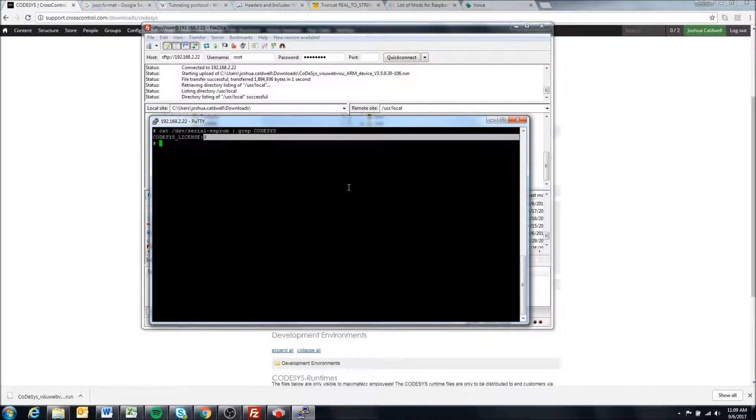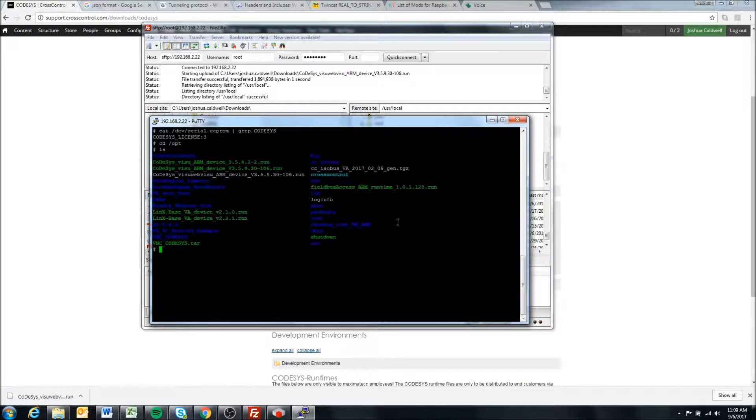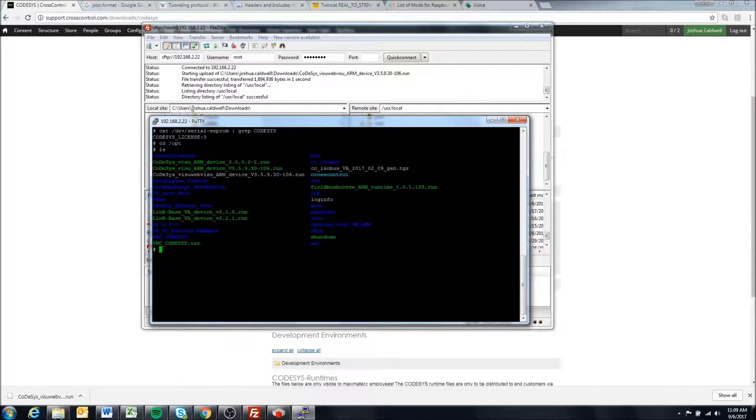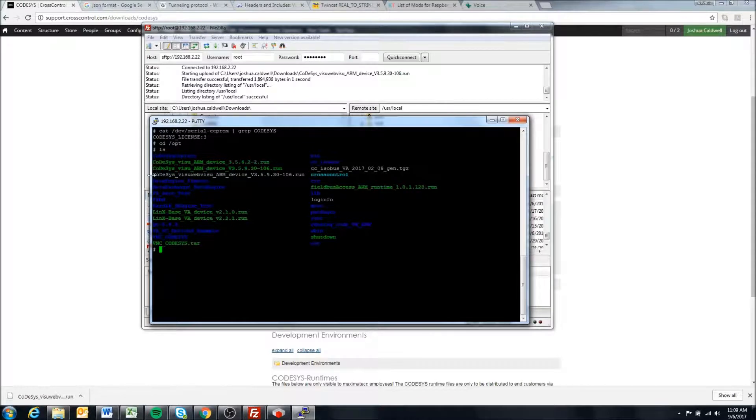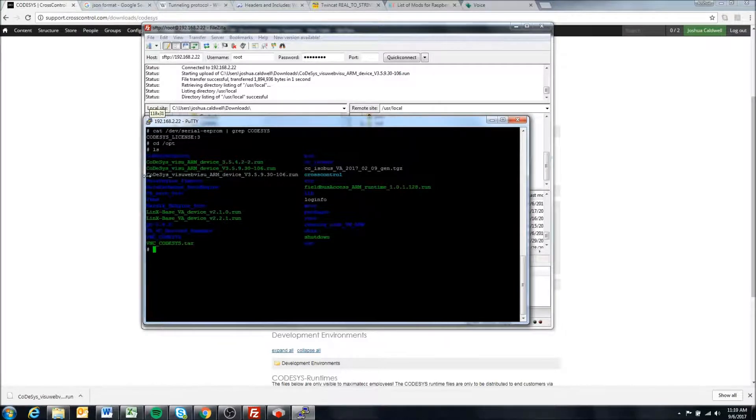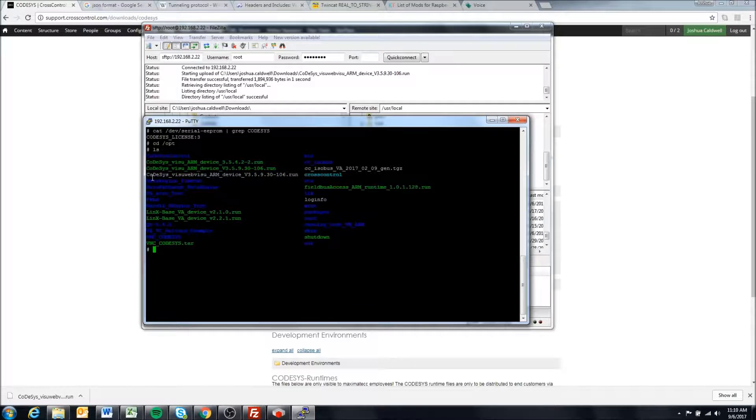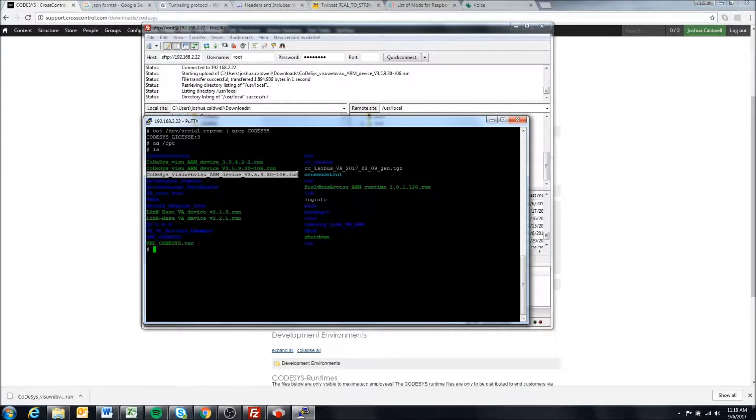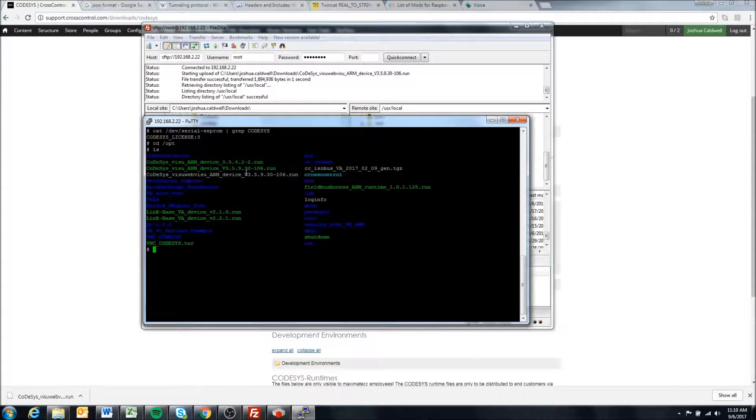Now I'm going to come into Putty again and type cd opt to move to the opt directory and check out what I have at the opt directory. Mine's pretty full because I'm doing a lot of stuff, but you can see the file that we've transferred over. This is the file, the Codesys visu web visu ARM device that we just transferred. This is the runtime file we want to install. You'll notice that it's grayed out, so this means it is non-executable.